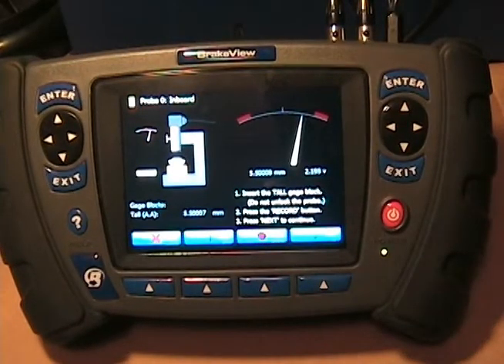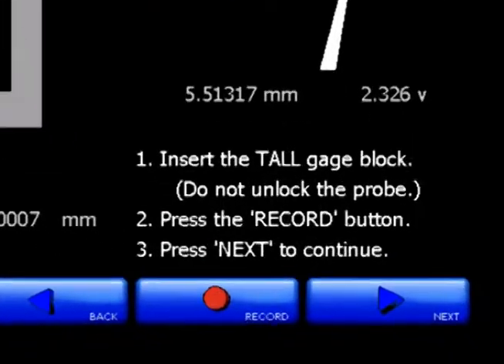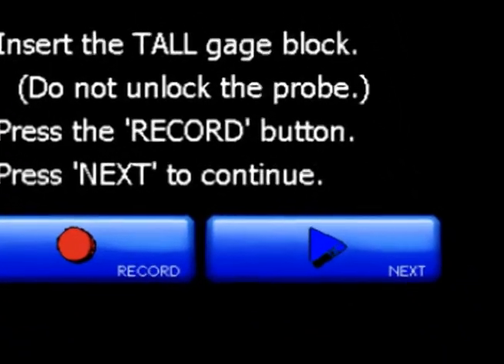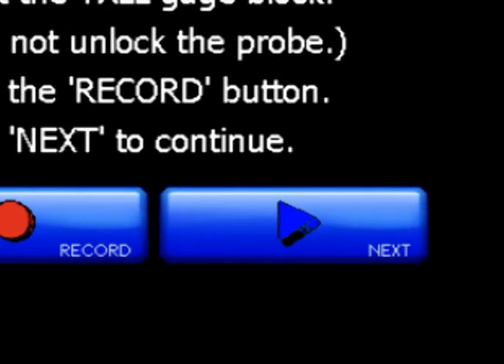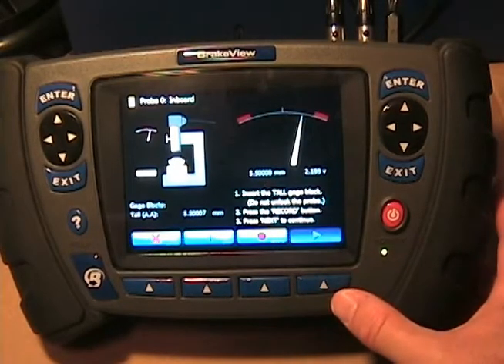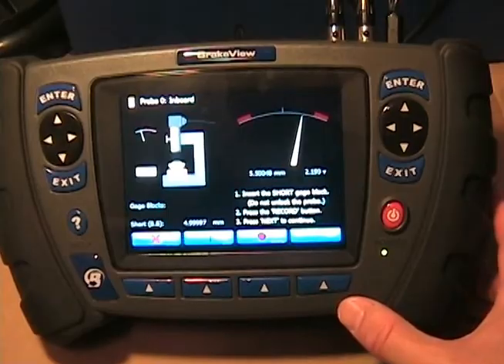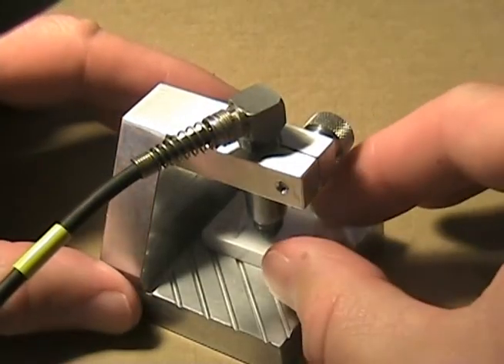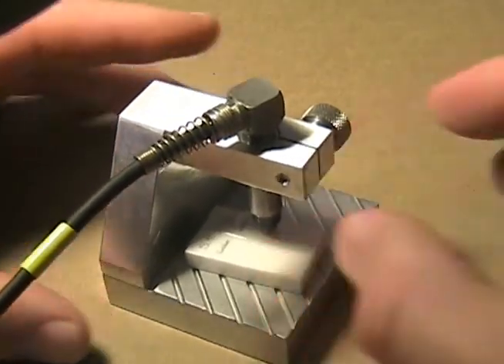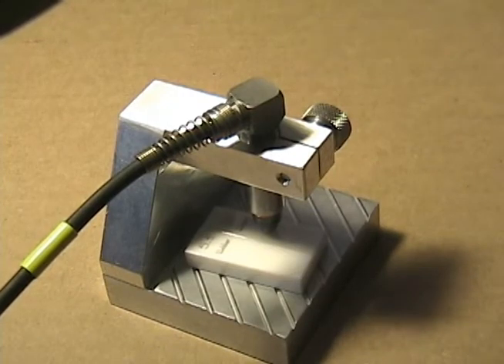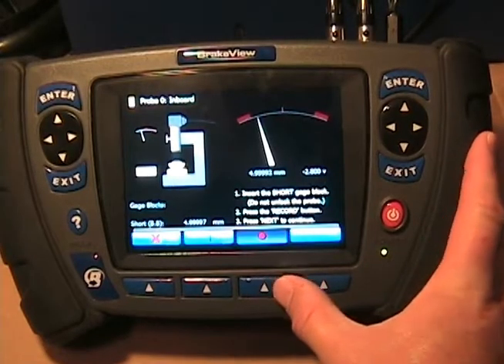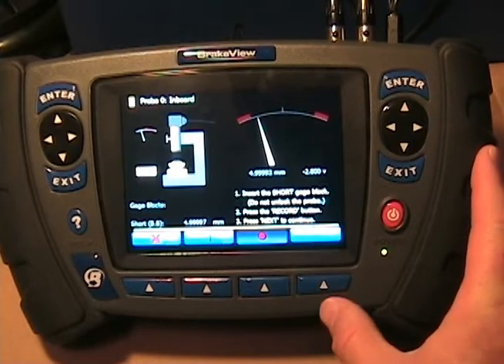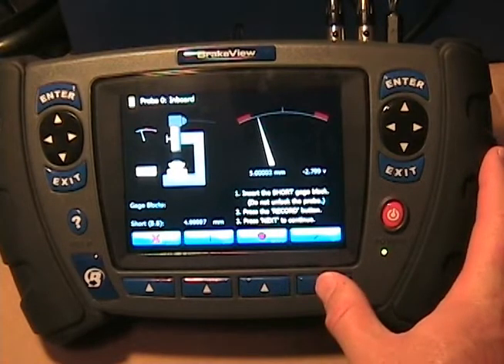After a few seconds, the system will have collected data on that tall gauge block, and the next button becomes available. On the far right side, it says next. We can go ahead and press that button, and now we are prompted for the short gauge block. Let's place the short gauge block underneath the probe and move our hands out of the way, and let's press the record button there. After a few seconds, we are again presented with a next button.